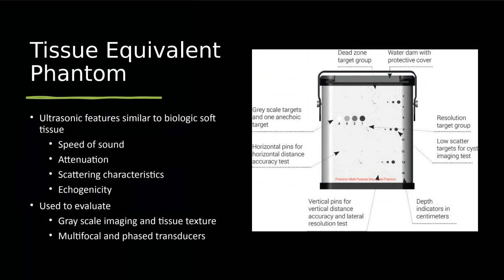One of those phantoms that are commonly used: if you happen to see a physicist come in for preventative maintenance, you'll probably see them carrying these big boxes. Those are these phantoms. The tissue phantom is really multi-purpose for them because it is the equivalent of human tissue. So it's going to have the same exact speed of sound, attenuation factors, scattering characteristics, and echogenicity levels, and we're using it to evaluate the entire grayscale imaging and tissue texture.